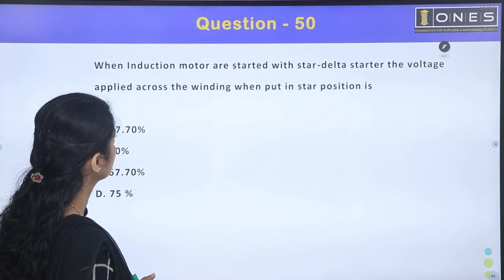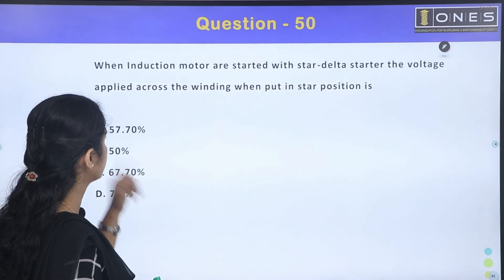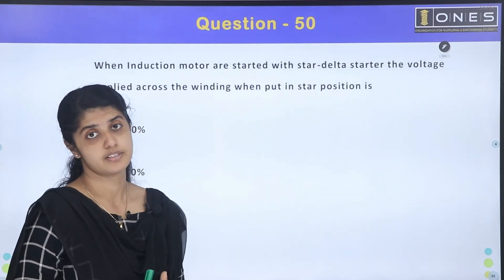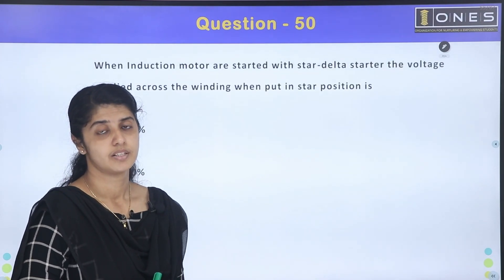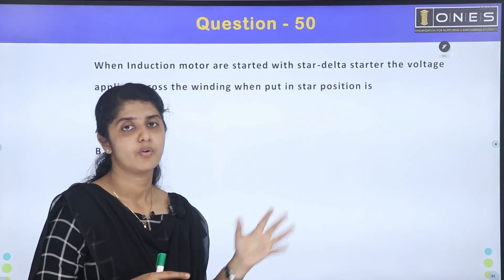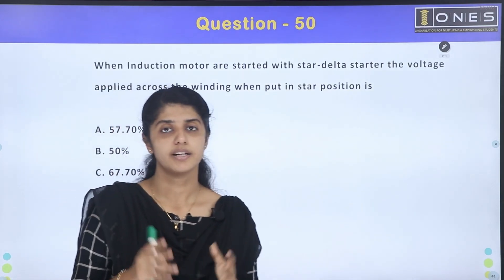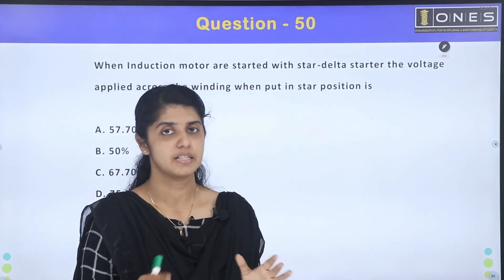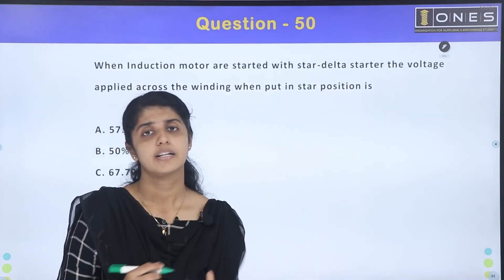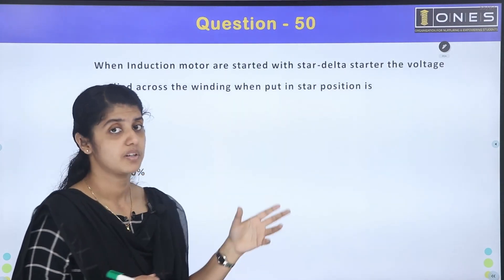When an induction motor is started with a star-delta starter, the voltage applied across the winding in the star position is reduced. In star connection, the phase voltage is VL divided by root 3, which means the winding receives 1 by root 3 times the line voltage.